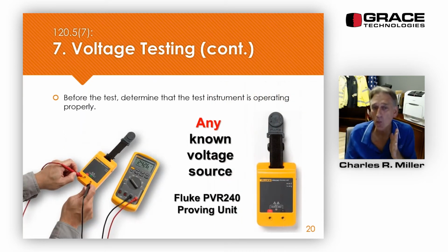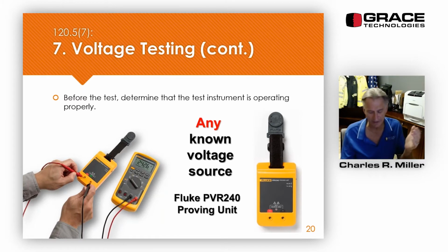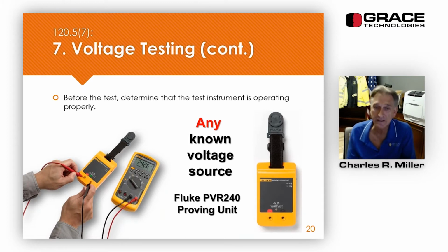All right, we have to check our meter before testing for the absence of voltage. Then after we check for the absence of voltage, phase to phase and phase to ground, we have to test our meter again. Fluke makes a device, it's called a proving unit, and it's a great little device. There's 4 AA batteries that go in here, and you're seeing on here it's somewhere around 240 volts that it puts out. It has a switch on the side for AC and DC. All right, so testing for the absence of voltage, we have to make sure our portable meter is working correctly on any known voltage source before we test for the absence of voltage.